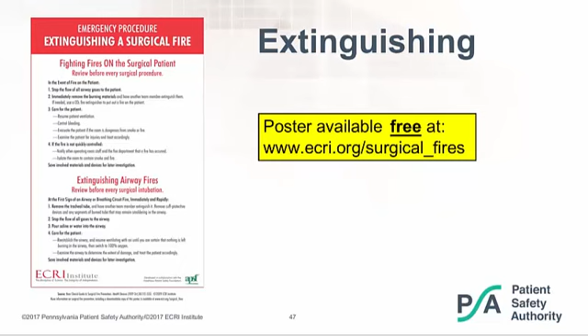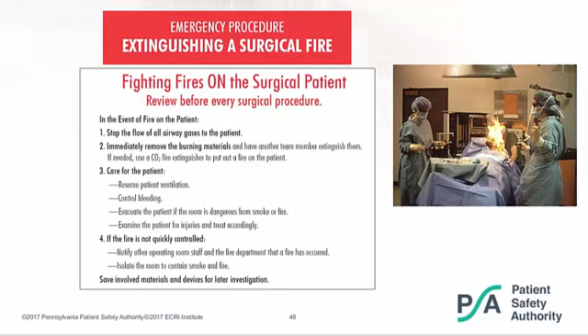Don't make them. As far as extinguishing is concerned, if the fire is on the patient, the recommendations are to stop the flow of all gases to the patient as you immediately rip what's burning off of the patient. If needed, with the materials that are thrown to the floor, or, though we know of only 3 cases in 40 years, if the fire is still burning on the patient, use a CO2 fire extinguisher to put out that fire. You would then care for the patient and, as necessary, quickly notify the front desk in the OR that a fire has occurred for which broader action might be needed. We know of no operating room fire that's ever gotten out of the operating room and affected anyone else in the other operating rooms themselves.